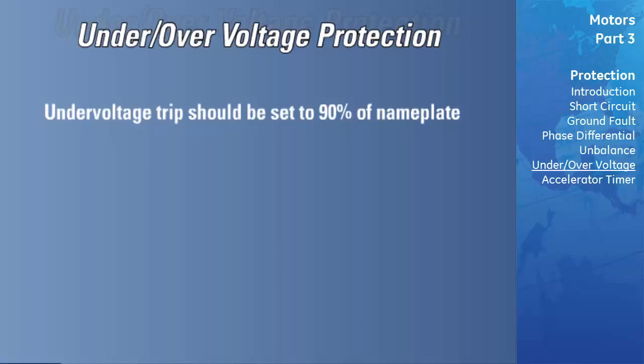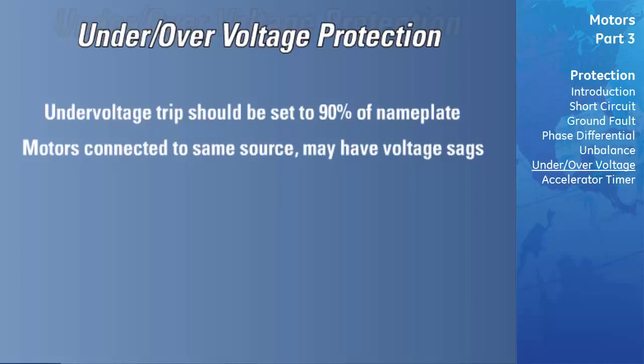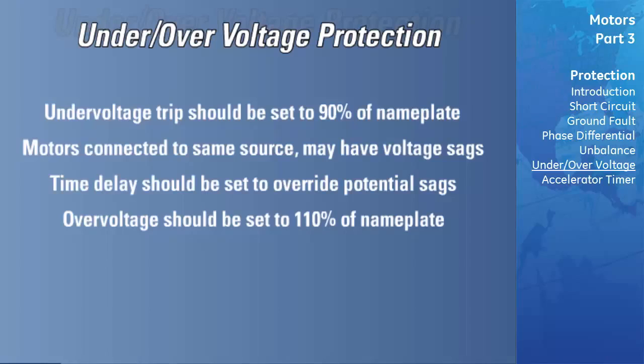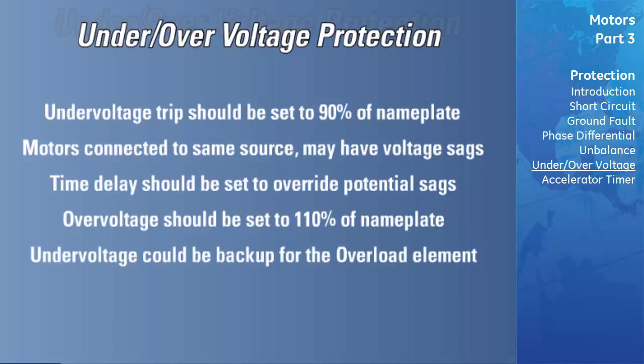The under voltage trip should be set to 90% of nameplate, unless otherwise stated on the data sheets. Motors connected to the same source may experience a temporary under voltage when one of the motors starts. To override these temporary sags, a time delay set point has been incorporated into the under voltage element. The over voltage element should be set to 110% of the motor's nameplate, unless otherwise stated. The under voltage element can be considered as backup protection for the overload element. If the voltage decreases, the current will increase, causing an overload trip. In some cases, if an under voltage condition exists, it may be desirable to trip the motor faster than the overload element.